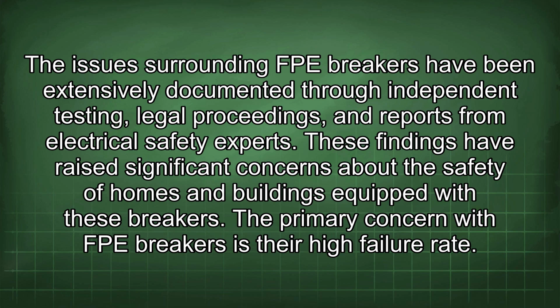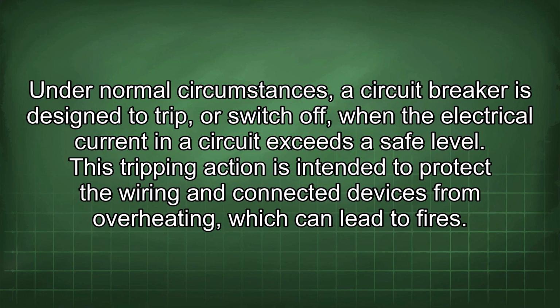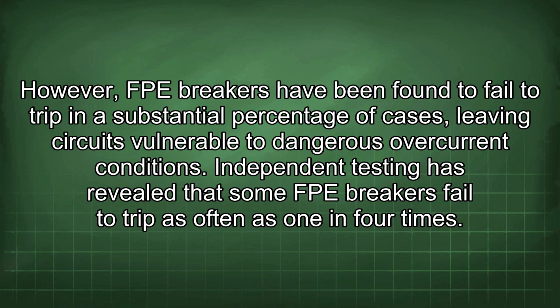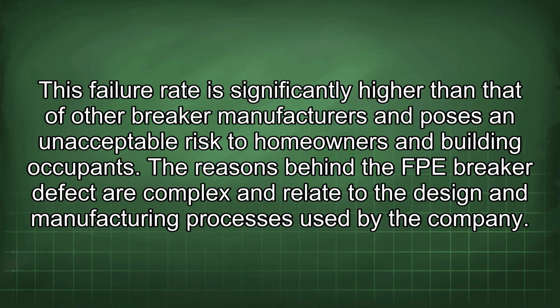The primary concern with FPE breakers is their high failure rate. Under normal circumstances, a circuit breaker is designed to trip or switch off when the electrical current in the circuit exceeds a safe level. This tripping action is intended to protect the wiring and connected devices from overheating, which can lead to fires. However, FPE breakers have been found to fail to trip in a substantial percentage of cases, leaving circuits vulnerable to dangerous overcurrent conditions. Independent testing has revealed that some FPE breakers fail to trip as often as 1 in 4 times. This failure rate is significantly higher than that of other breaker manufacturers and poses an unacceptable risk to homeowners and building occupants.